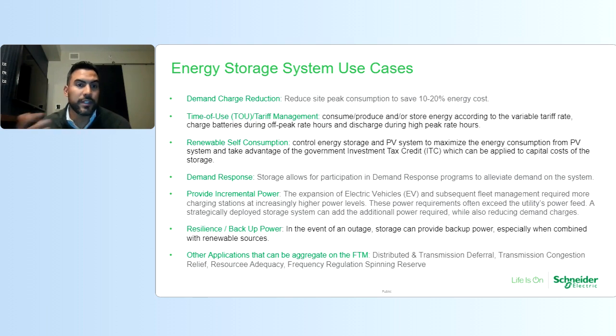So if we go through just the list of energy storage use cases, you can see there's quite a few here. I would say one of the primary reasons why these energy storage systems get adopted into a facility is demand charge reduction, right? You're hitting peak values throughout your utility rates. You go over, and then once you hit that utility demand charge, sometimes you get charged that rate for the rest of the month, for a longer duration of that period. And really, once you hit that demand charge, your utility rates kind of skyrocket. So most energy systems are implemented here to reduce those demand charges, keep you within the allocated limit.